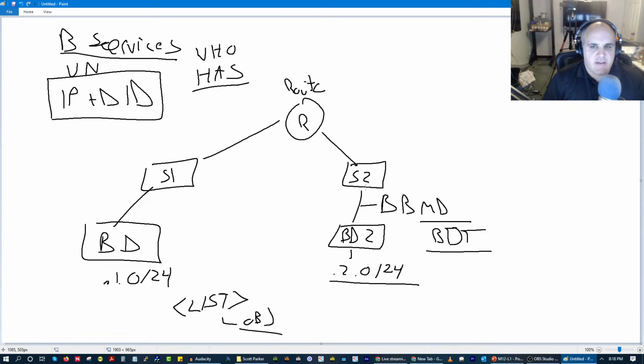It will then get sent to the switch, which will use the Address Resolution Protocol to figure out which port to send it on, and it will send that encapsulated IP message, encapsulated by an Ethernet frame, to the BACnet device, and then it'll go back up the OSI model layers.